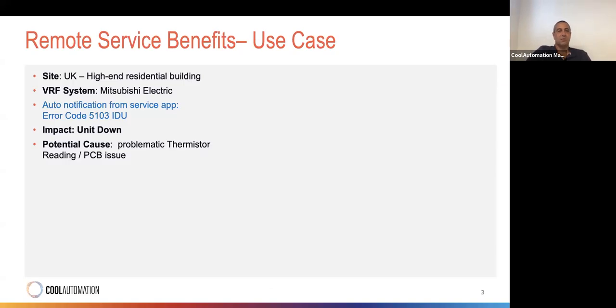I want to take you through a use case we experienced using remote services. This is a real site in the UK, a high-end residential building with a Mitsubishi system. The issue was an error code, in this case 5103, which means there's a problem with one of the thermistors. The impact is the unit is down.